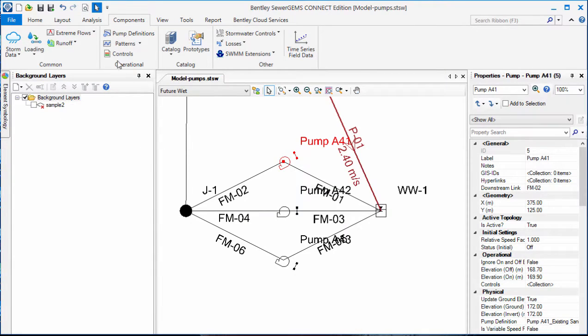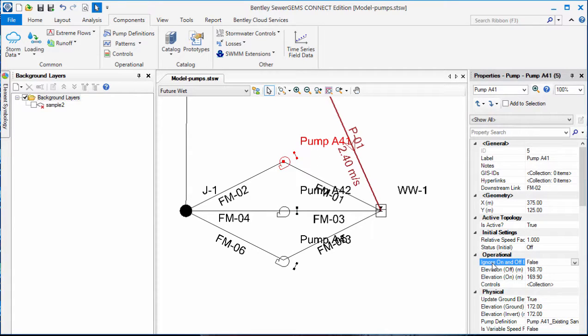In order to apply the logical controls, you would return to the pump properties and set ignore on off elevations to true. When you do that, the on and off elevations in the properties will be ignored and the controls in the controls manager will be used instead.